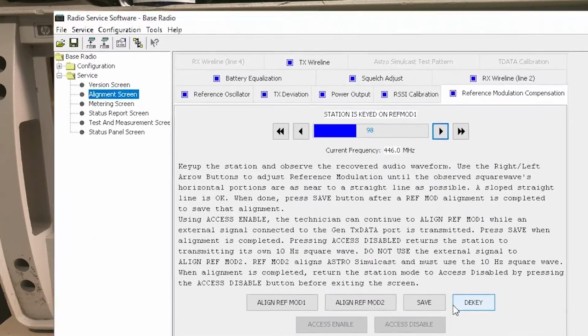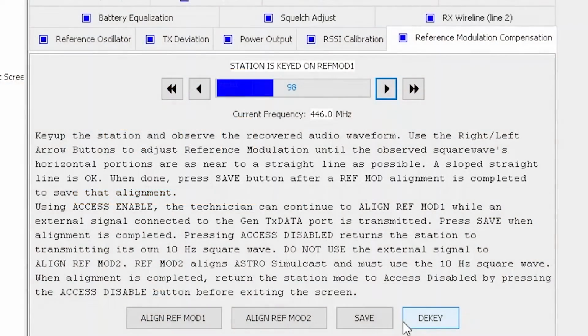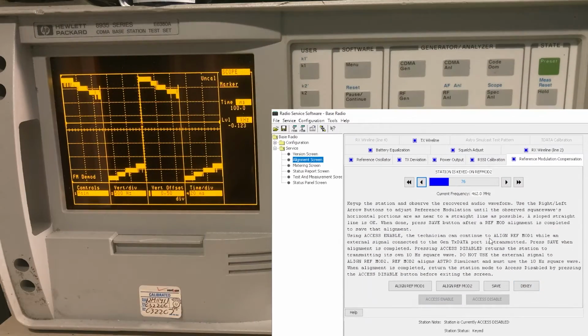If you read the blurb in the alignment tool here, it says slanted lines on the horizontal are perfectly fine - as long as they're not round, your reference compensation is good enough. Same exact procedure here for the second reference frequency, just trying to get those legs as straight as possible, and I think this looks pretty good.